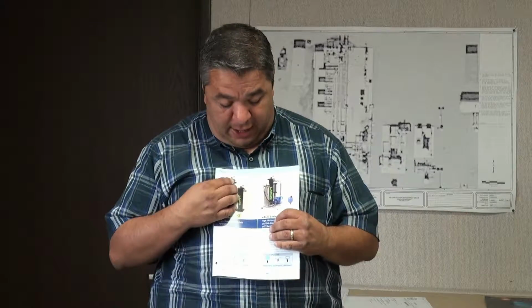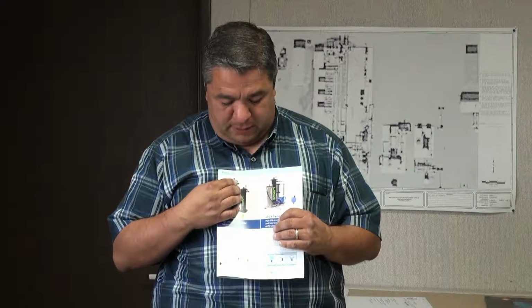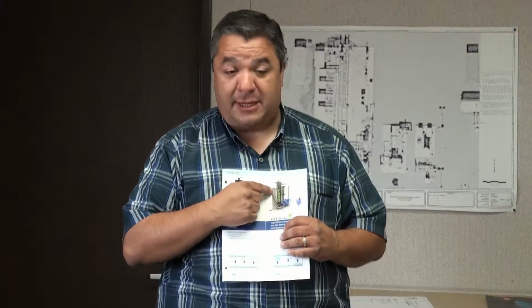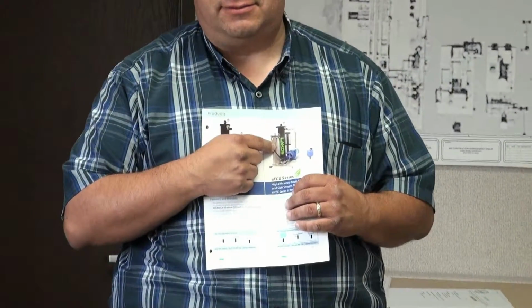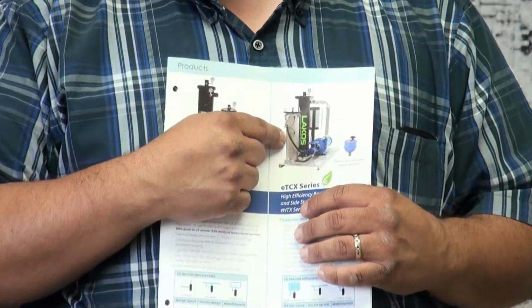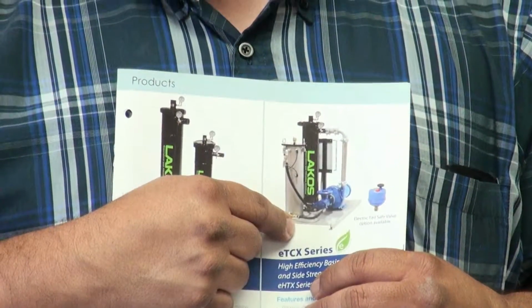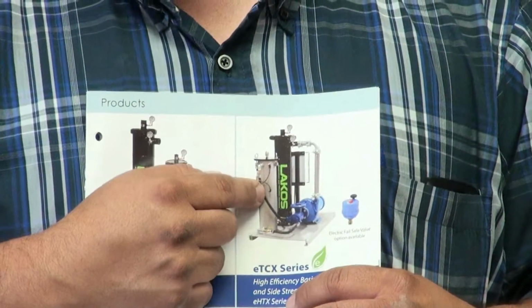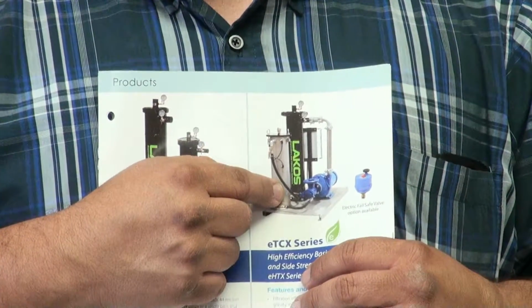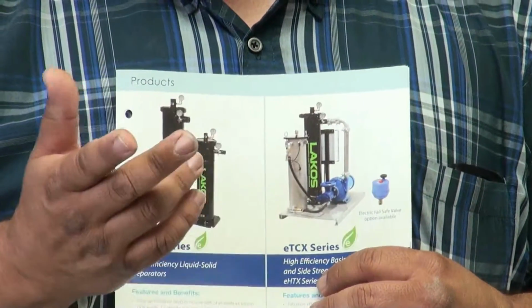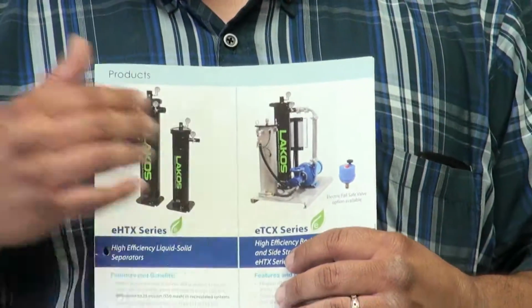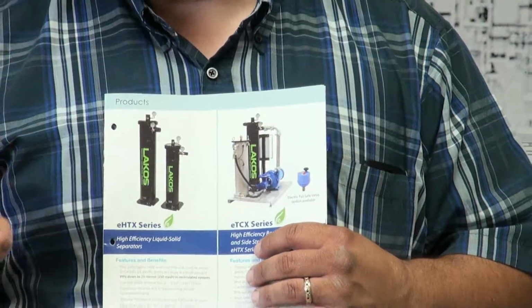Now, we have the Lakos separator, we have a pump, and we have an SRV, which is a solid recovery vessel, and it's stainless steel. Inside that solid recovery vessel is the bag filter. We've talked to Dan about this - those bags are washable bags, you can wash them. They're good depending on the debris that's coming out or how bad the startup was.